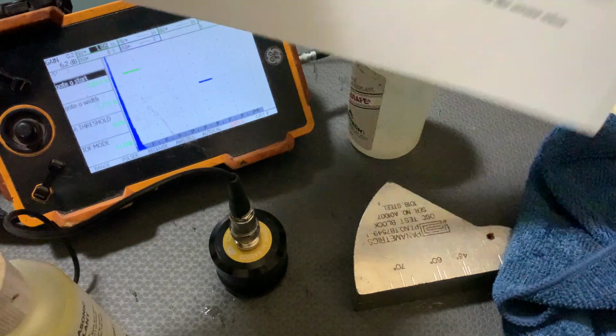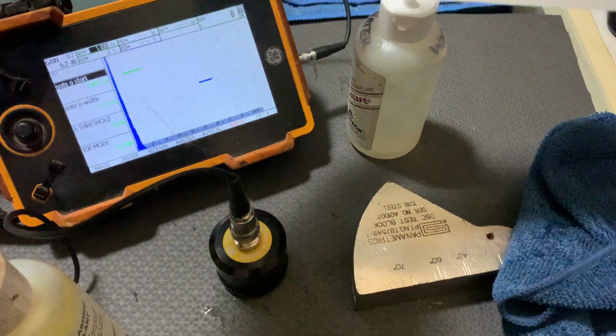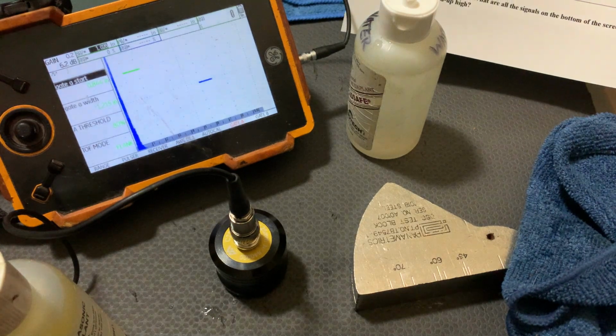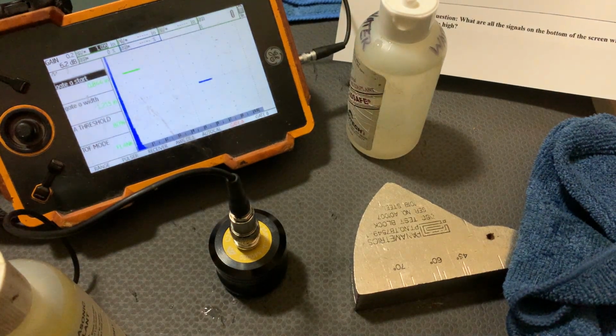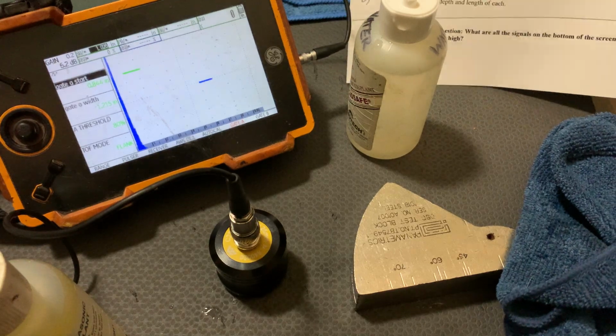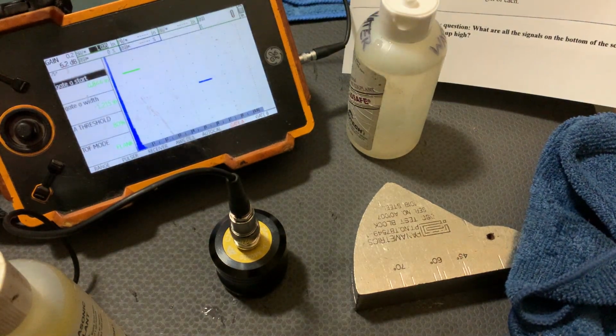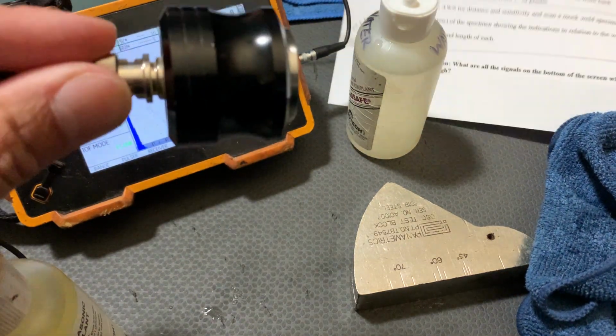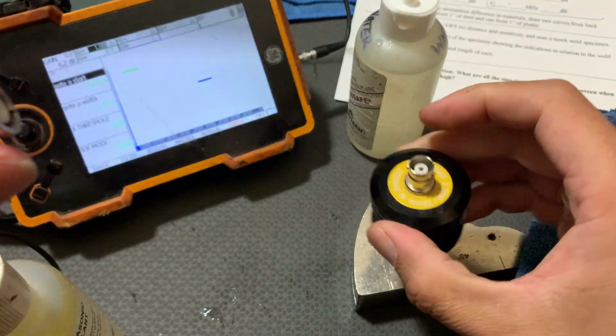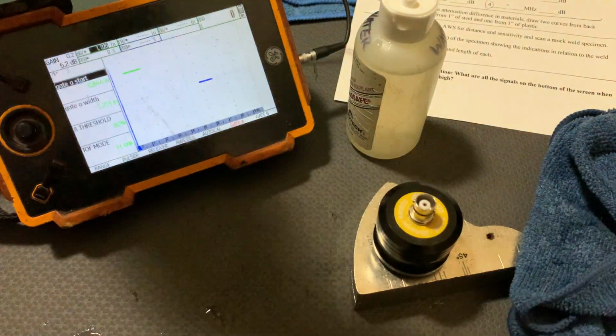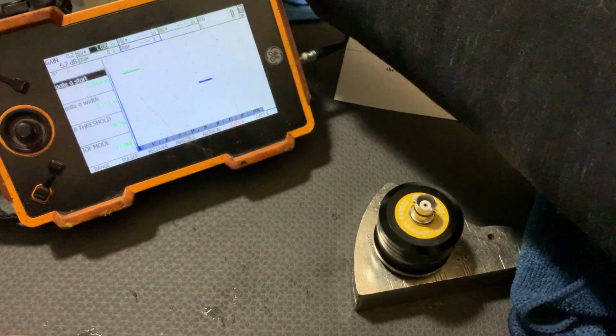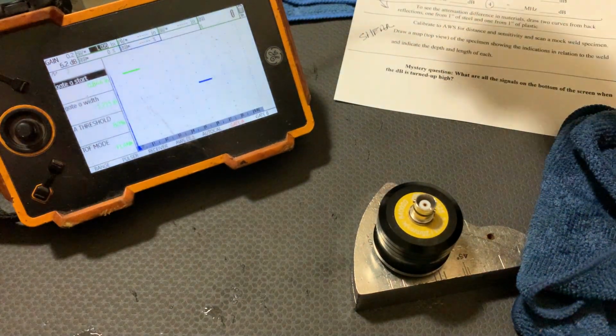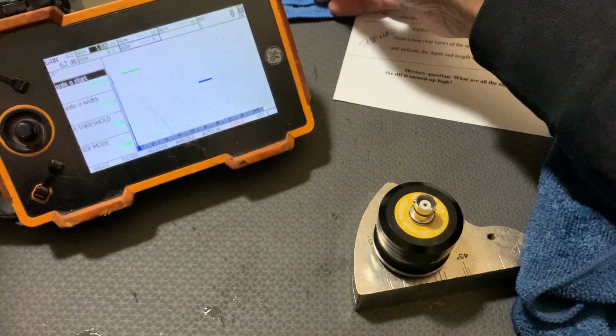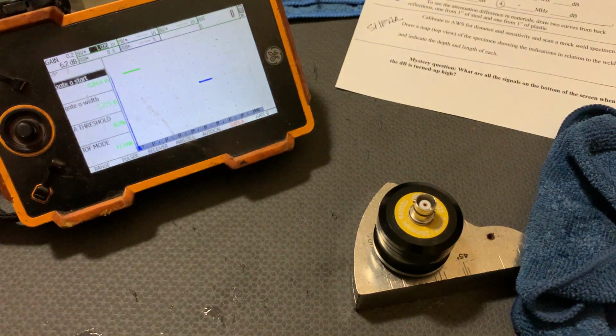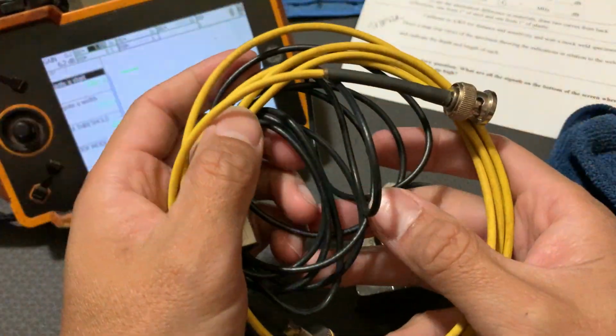Okay, that's second assignment. Third assignment is couple 4 different coaxial cables and transducers. Note their difference in decibels, each at 80% screen height. So what you do with this one is keep your same transducer that you're using. Keep this guy. Change out the cable you have now for some of these other cables we have set out.